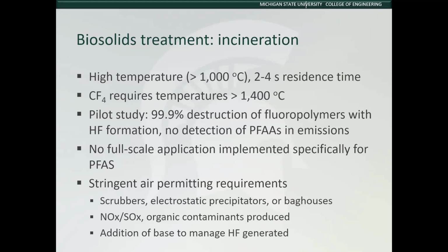As far as I am aware, however, there were no full-scale applications implemented specifically for PFAS incineration. As with all incinerators, stringent air permitting is required. Particulates can be removed with scrubbers, electrostatic precipitators, or baghouse filters.